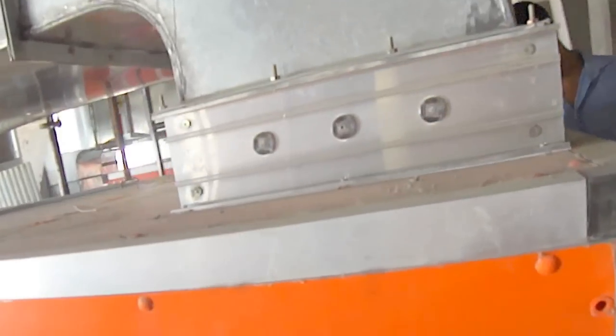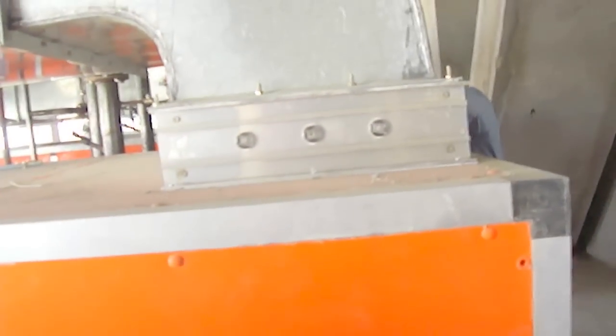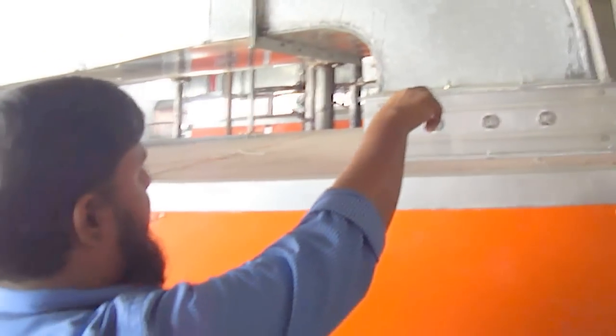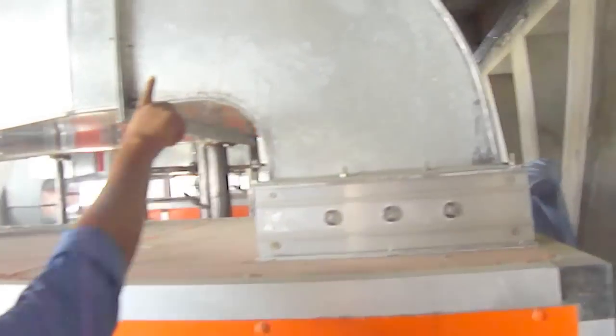This side is good. Here you see the outlet, or the inlet, sorry, the return air has this VCD, and this is the elbow, you know that. And what about this one? These are flanges. And in between the flanges, what is that? Gasket. And after the gasket, after the leak test, you'll find the sealant also. So after that leak test, we can go for sealant. But presently, you can see the gasket is white, rubber. And you see that nut, this bolt is not properly tightened.